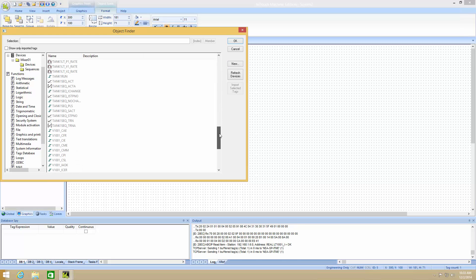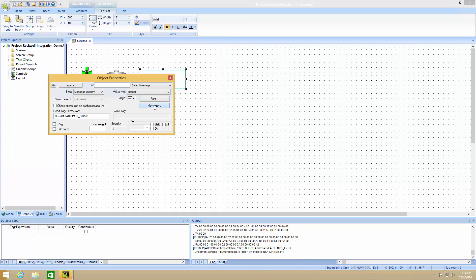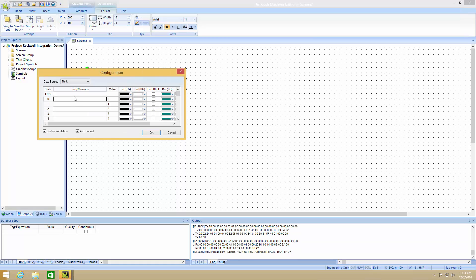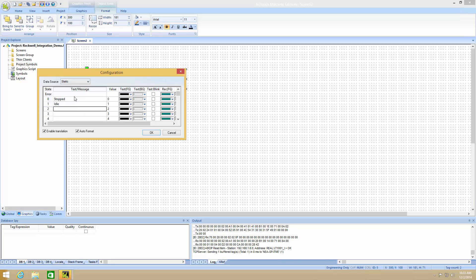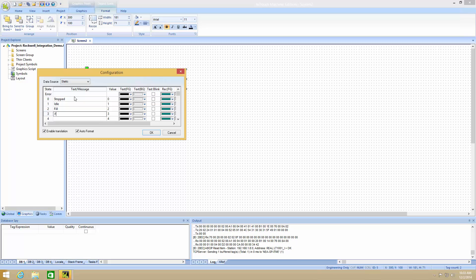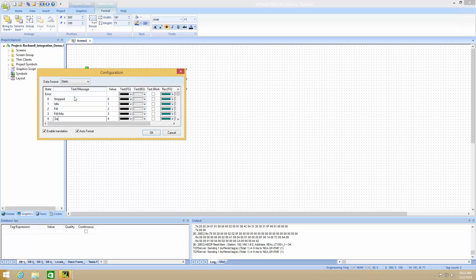In this case it's a tank sequence step number. And I can also assign the messages to this. So I happen to know that when the tank sequence step number equals zero, the system is stopped. When it's equal to one, it's idle; equal to two, it is fill; three is mix; and four is drain.